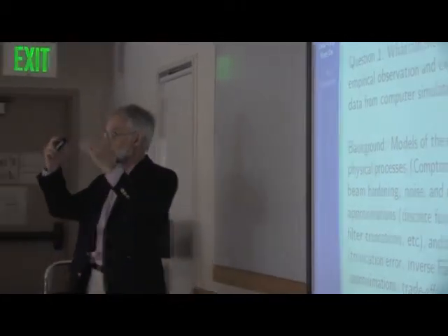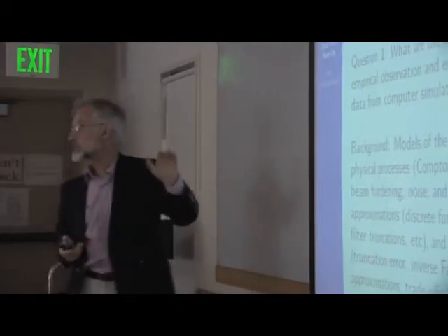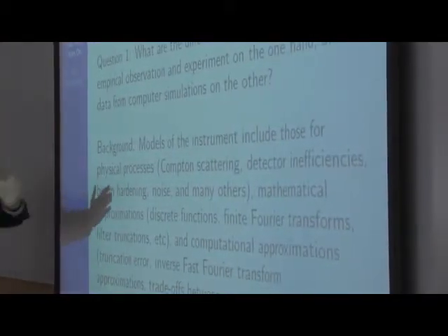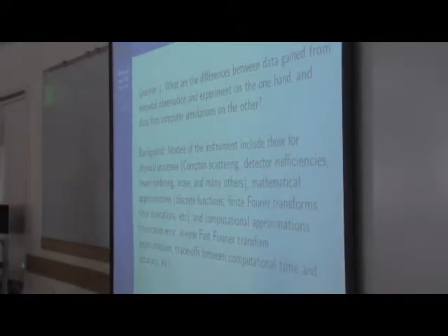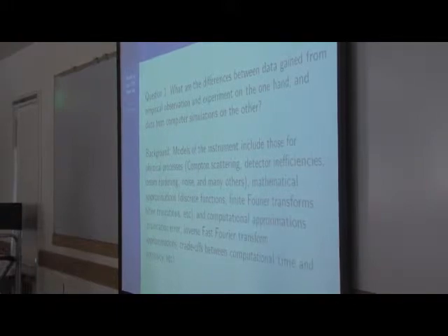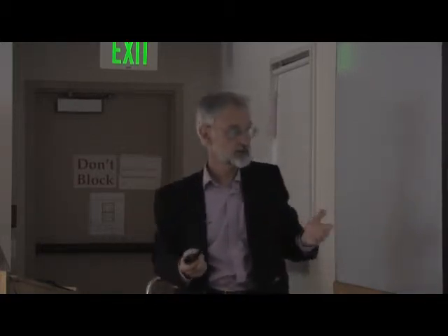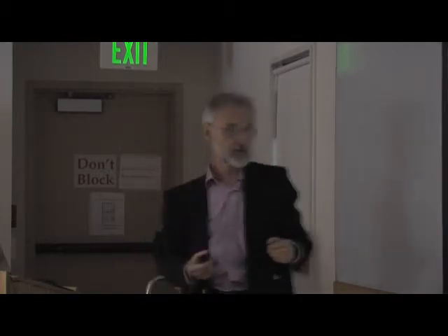Remember the hierarchy that Pad directed our attention to — lots and lots of models playing a role in getting from the abstract theory down to the data. For example, you've got Compton scattering: an X-ray that starts out on a given ray will sometimes be deflected and picked up by a detector on a different ray — you've got to correct for that. There are inefficiencies in the detector that have to be corrected for. There's beam hardening — that is, low-energy X-rays never make it to the detectors, so you've got to correct for that. There's noise, and there are many, many others. So there are lots of models involved just in appraising the physical processes.